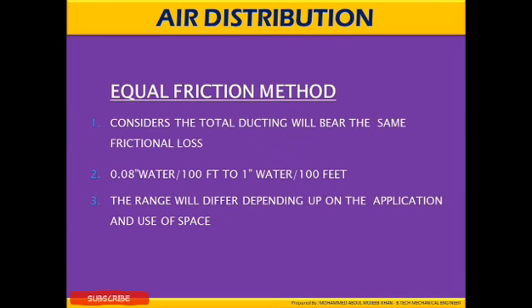Equal friction method. Consider the total ducting will bear the same friction losses. For example, 0.08 inches of water per 100 feet. This is a typical example where we need to consider the ducting will bear the same friction loss throughout the sizes. The range will differ depending upon the application and the uses of the space.